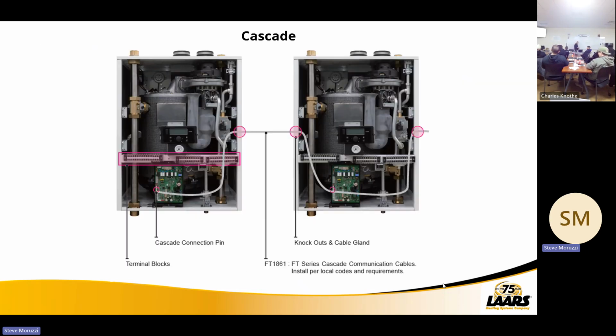So just a heads up on that. Your communication cascade cables plug into the boards, from one board through the knockouts to the next board, okay? So if you're cascading, try and keep these tighter together, and follow the instructions in the cascade manual for distance. Don't plan on putting these 4 feet apart and then trying to cascade them, because you can't cut those wires, redo them and resplice them. The cables are short, so follow those instructions.